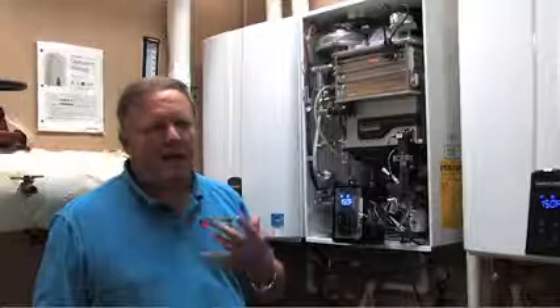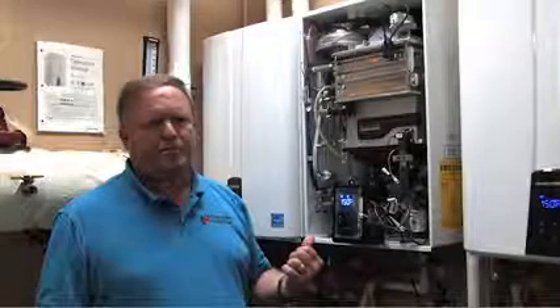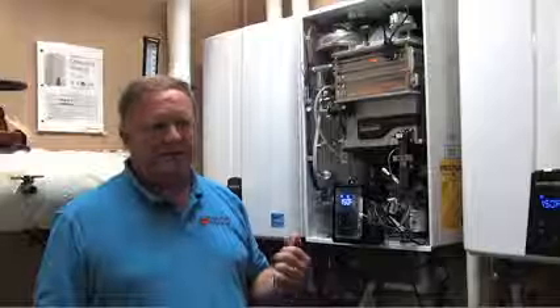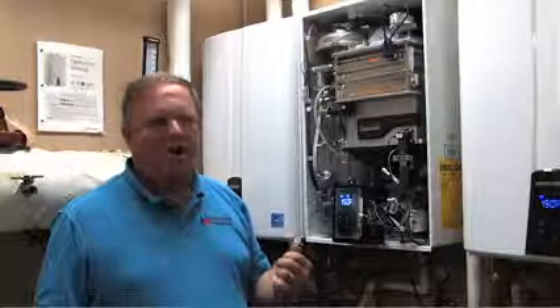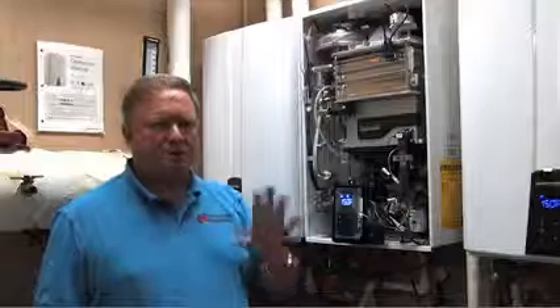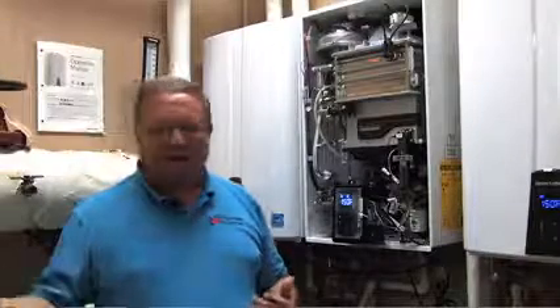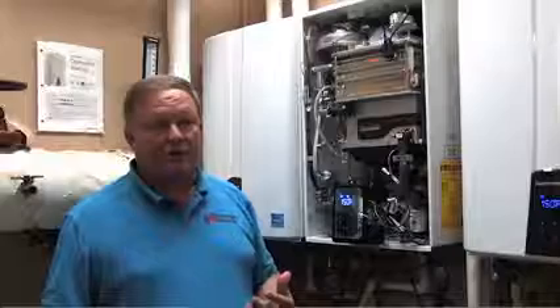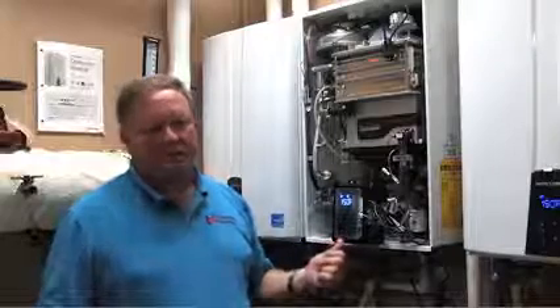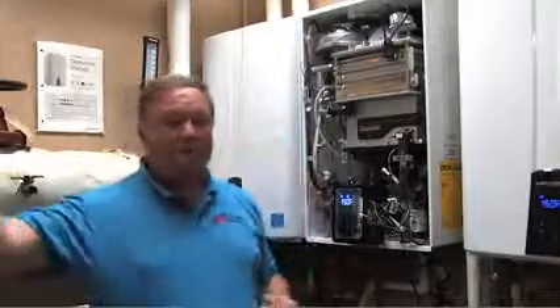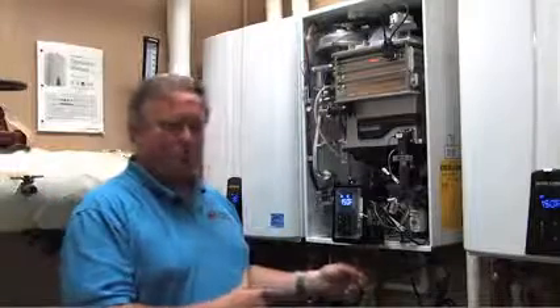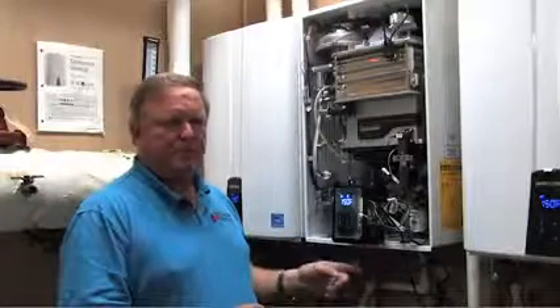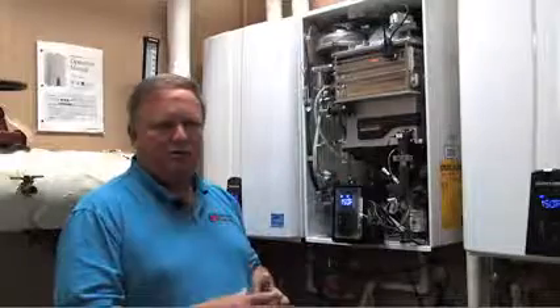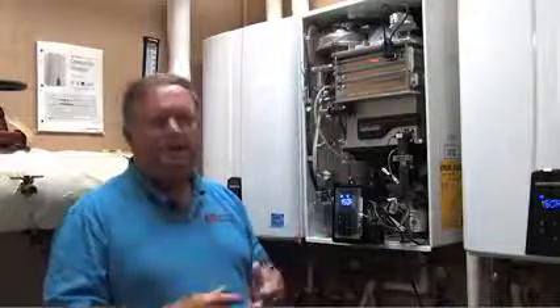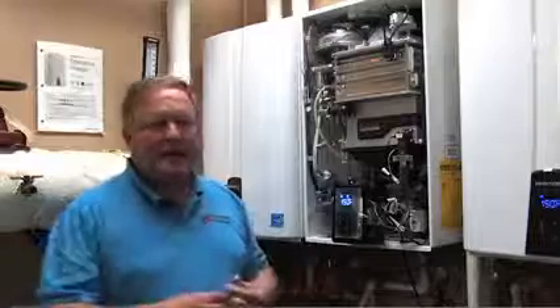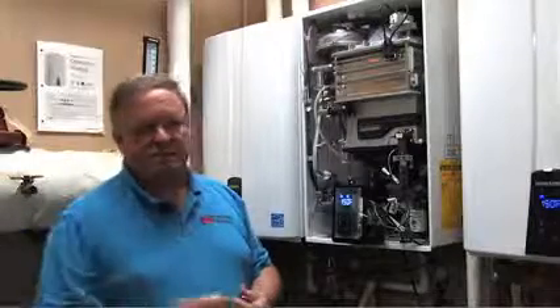The advantages of the internal pump are no small thing. This is what made us, as a company, look at this product to begin with. The pump saves thousands of gallons of water a year. Picture in a shower situation how most people are, where they have to hold their hand in the shower waiting for it to get hot. Now with this pump we can run what's called a return line, which will go to that farthest fixture and come back to the unit. When the temperature coming back to the unit drops to whatever its setting is, the pump will come on, keep that loop hot, so that when you turn on that shower, that sink, you get instant hot water.